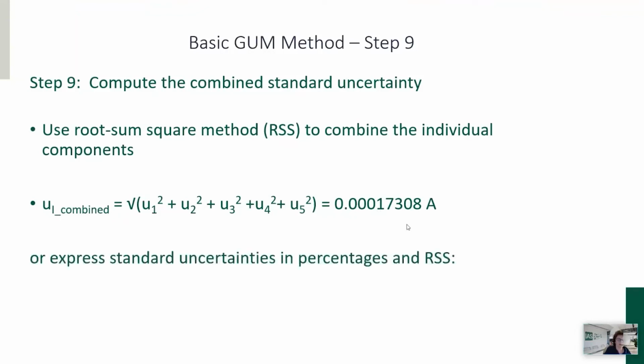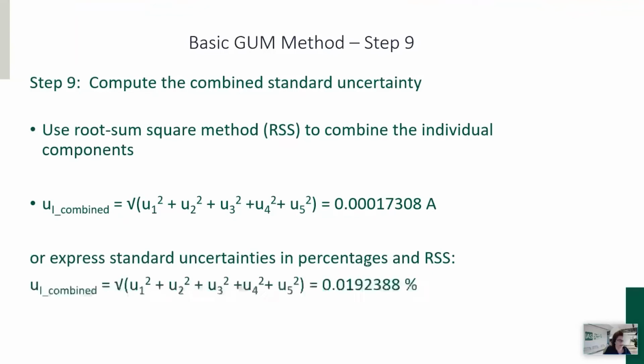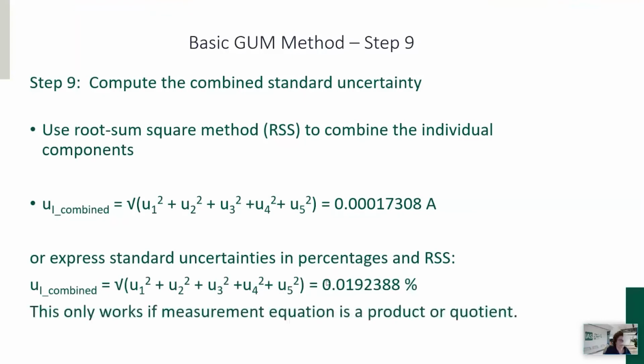I told you all about these sensitivity coefficients, but you could also root sum square the percentages I've computed, and come up with an uncertainty expressed as a percentage, roughly 0.0192 percent. As a test of these two different methods, I did the math this morning, and if you convert that percentage to amps, you come up with that very same result.